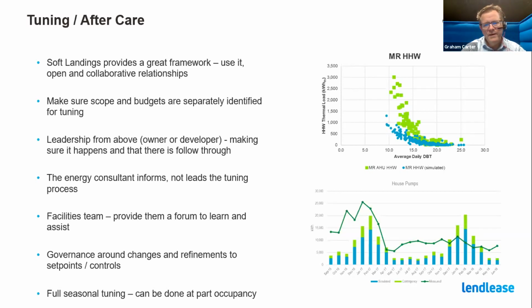Quite often there's a lot of changes made to set points and controls through the tuning process, and it's important that the base building design team governs that, and that it's locked away into a permanent memory of the control system rather than just a modification of the first image of the control system. We've quite often lost set point changes and controls changes, so it's really important that's tightly governed.